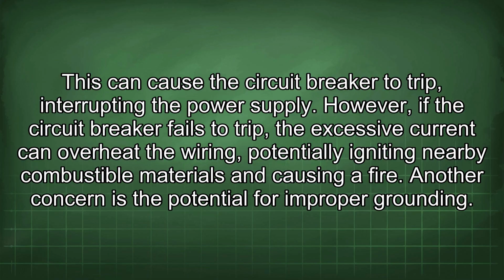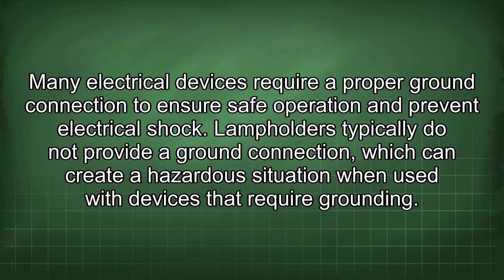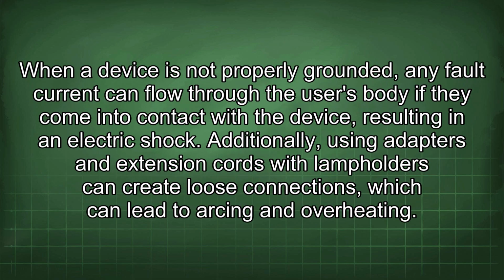Another concern is the potential for improper grounding. Many electrical devices require a proper ground connection to ensure safe operation and prevent electrical shock. Lampholders typically do not provide a ground connection, which can create a hazardous situation when used with devices that require grounding. When a device is not properly grounded, any fault current can flow through the user's body if they come into contact with the device, resulting in an electric shock.